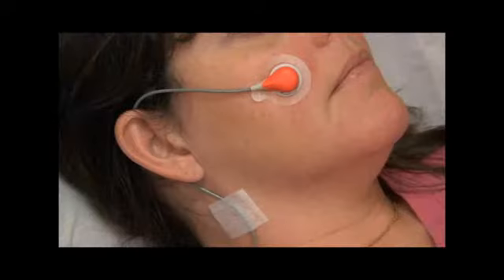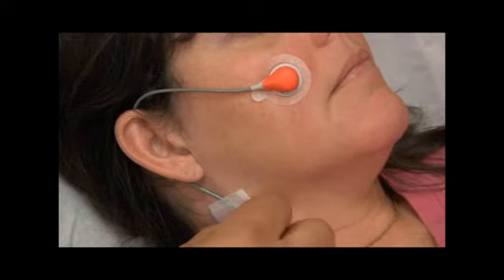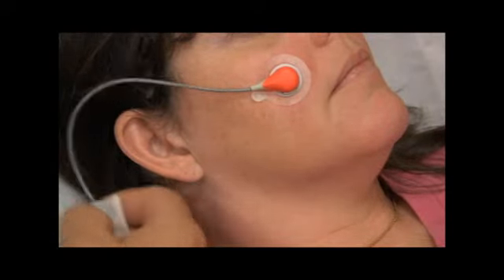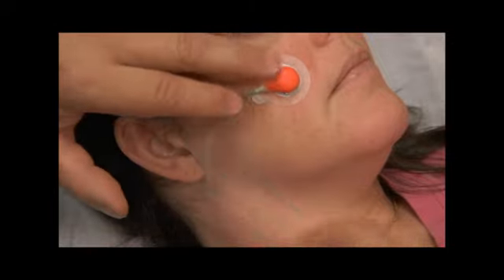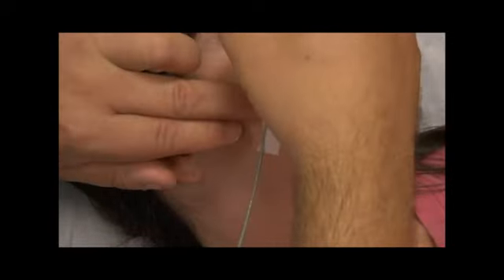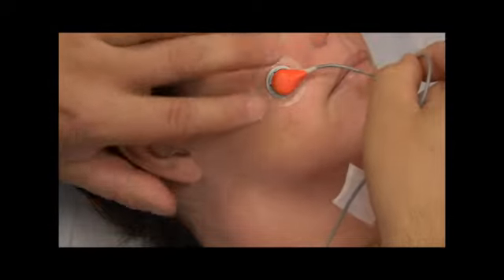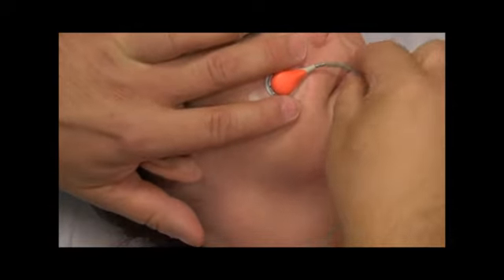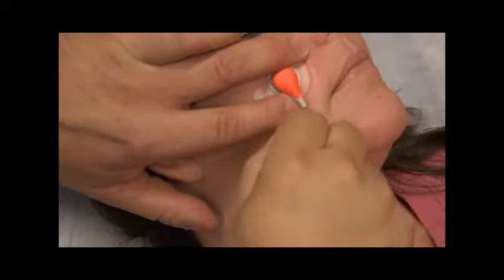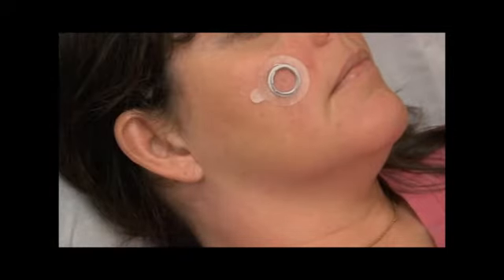Multi-site ring. Remove the adhesive tape from the sensor cable. Place a finger on either side of the sensor and rotate the sensor towards the index finger. As the strain relief of the sensor cable comes in contact with the fingernail on the index finger, continue turning and the sensor will be wedged from its seat as shown.